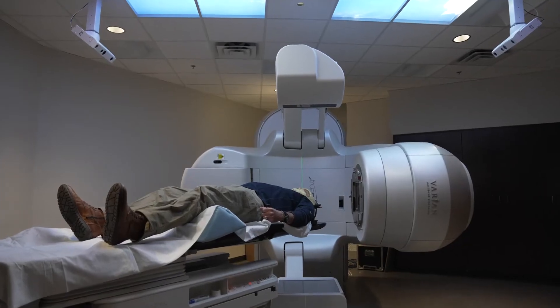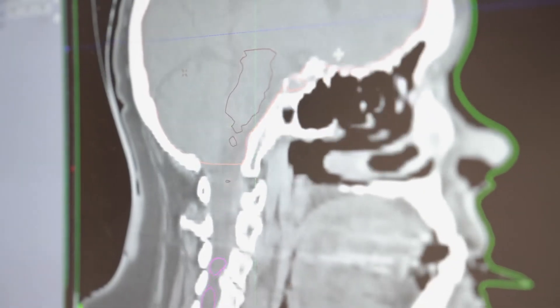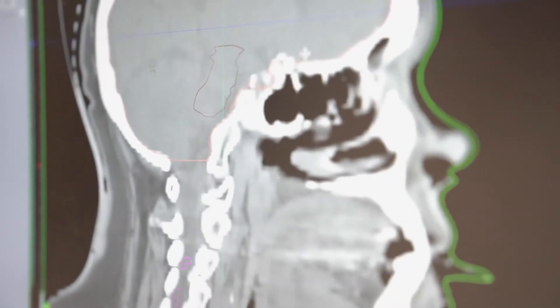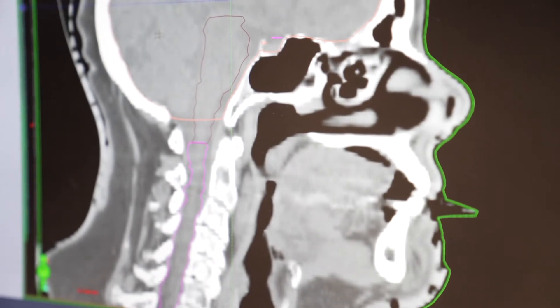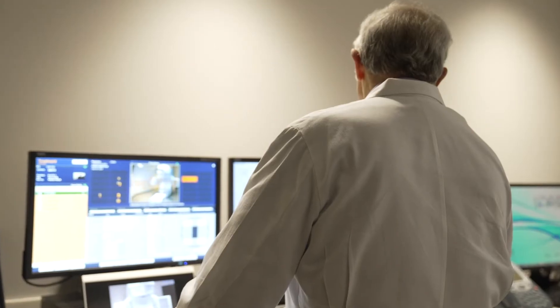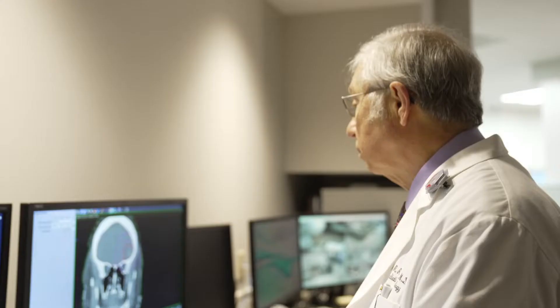If you look back in the cobalt days, the goal was to have a very uniform distribution of radiation from one side of the head to the other — it was very uniform. That was the theory and the necessity with that technology. Now we don't necessarily want to treat all those other areas of the brain to high dose. We want to keep the dose as low as possible.